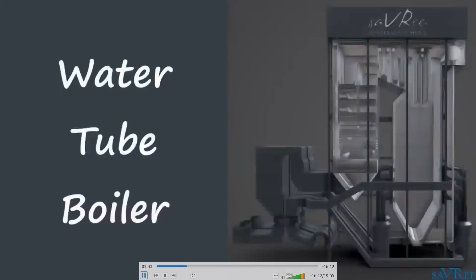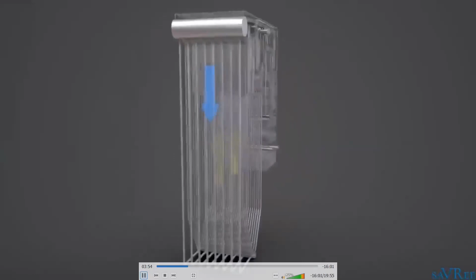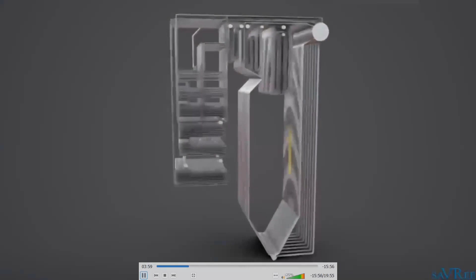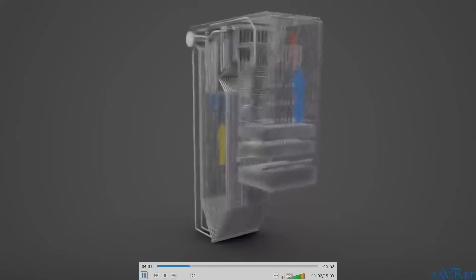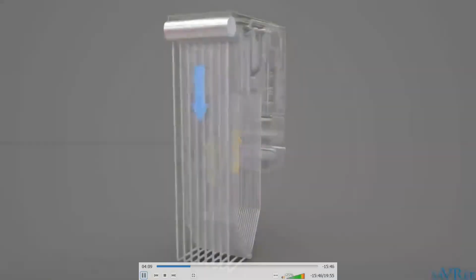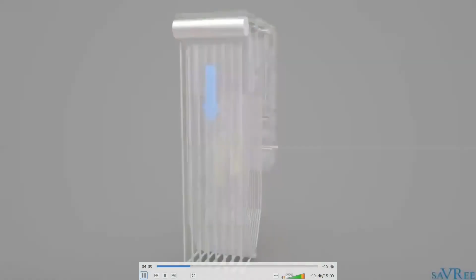The type of boiler we're using is a water tube boiler. Whenever you need a lot of steam at very high pressures, you're going to be using a water tube boiler. Steam turbines require steam at very high pressures, and that's why we use water tube boilers. But water tube boilers also generate a lot of steam. They're very large. They can be greater than 40, 50, 60 meters in height. And these are the boilers that power stations in the power generation industry always use.